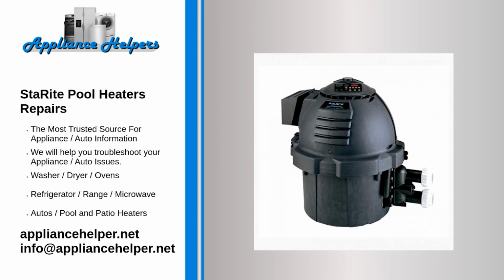Low water pressure can be caused by an improperly sized pool pump, dirty filters, closed or partially closed valves, an external bypass that needs adjusting, or the water connection being reversed. If you have ample water pressure, you may have a faulty water pressure switch that needs to be replaced.